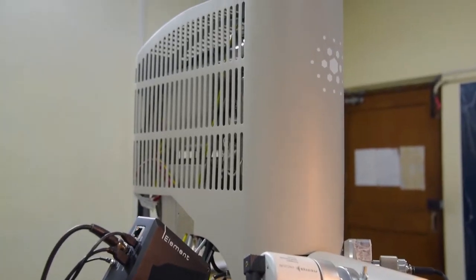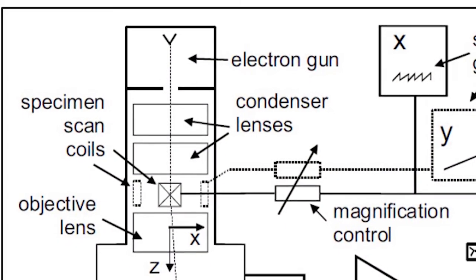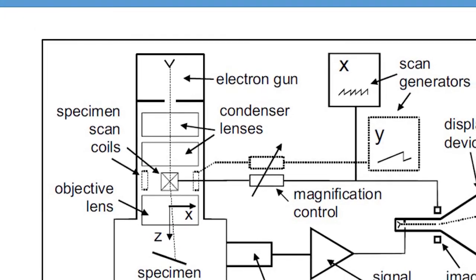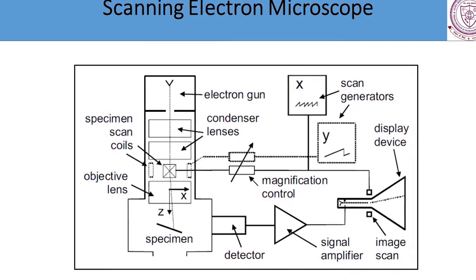Let us get back to the scanning electron microscope. It has an electron source right on the top of the equipment, and it has a condenser lens. A highly collimated beam, depending on the size of the area you want to scan, falls on the specimen. Because of the interaction of electrons with the specimen, it gives rise to varieties of electrons — these could be secondary electrons or back-scattered electrons — and they have specific applications that permit you to know the surface features, which in metallurgy and material science we call microstructure.